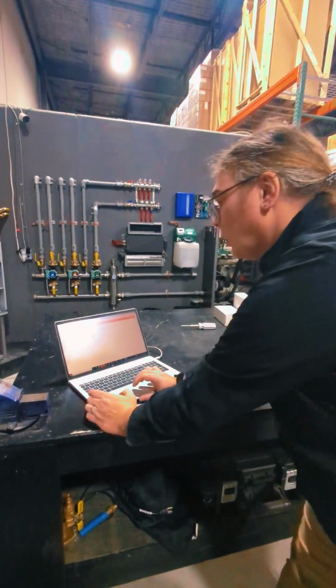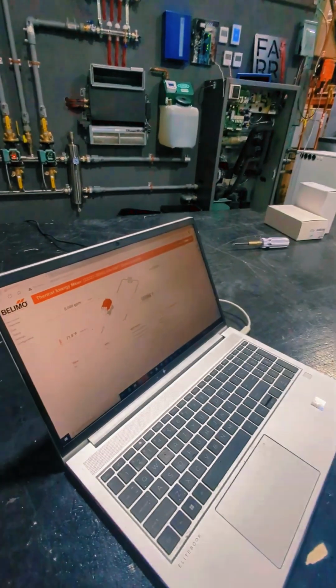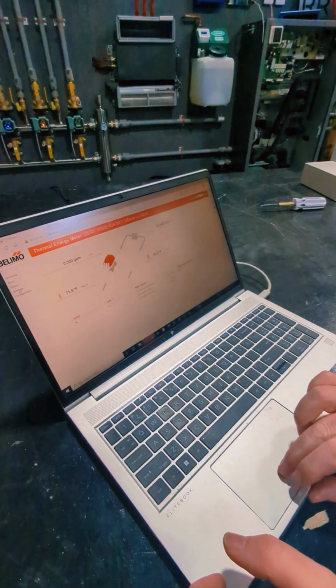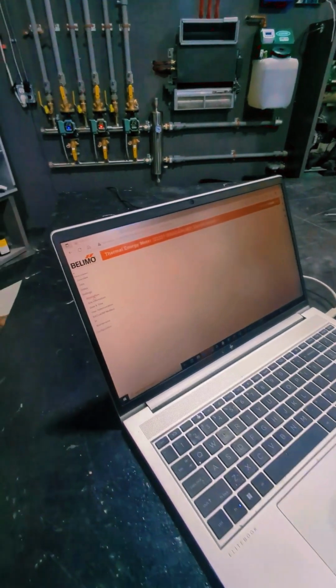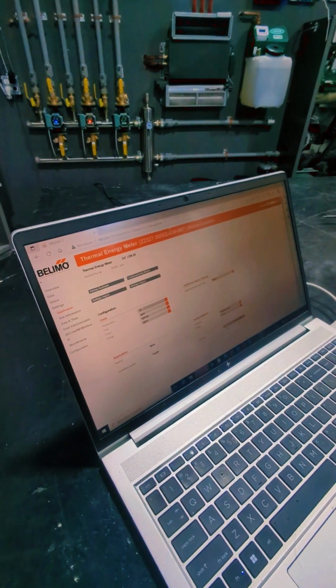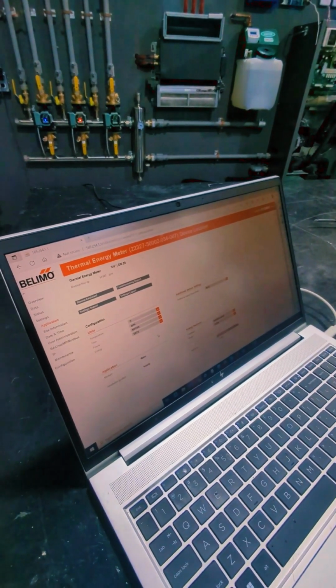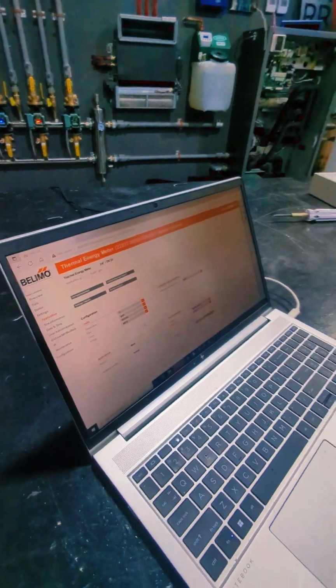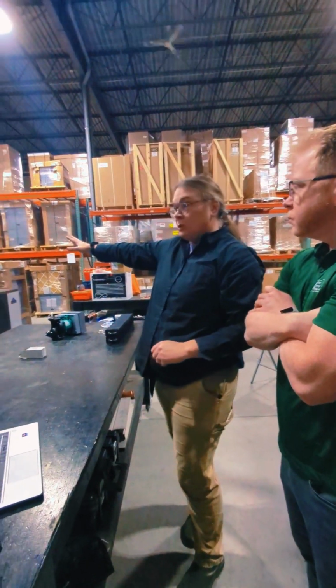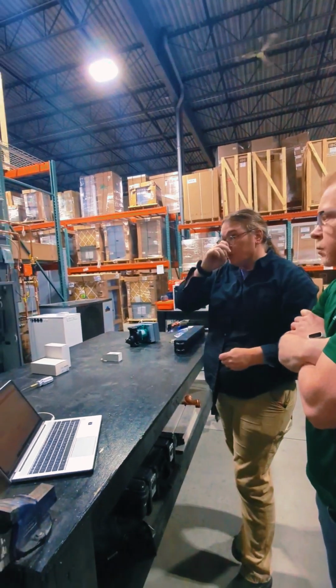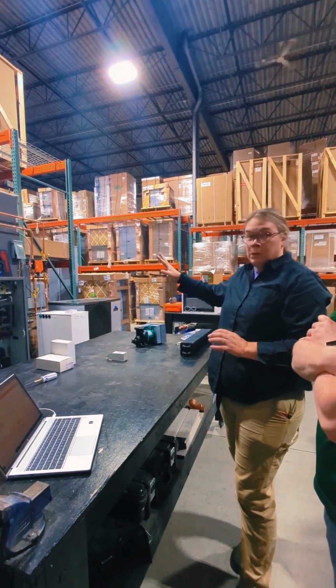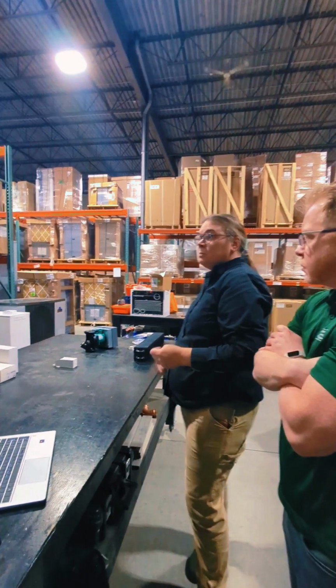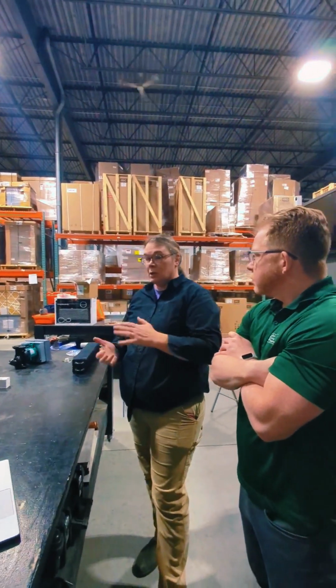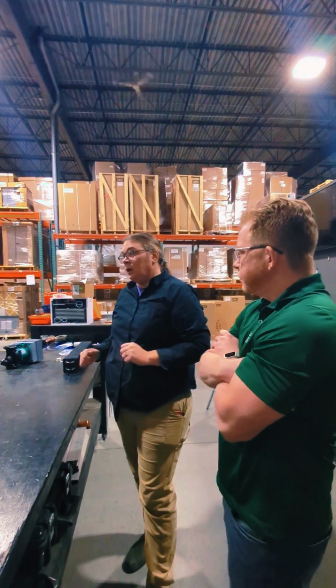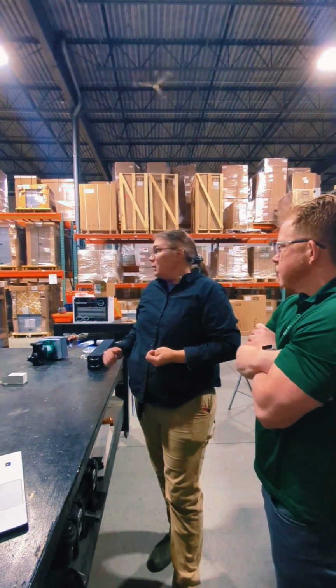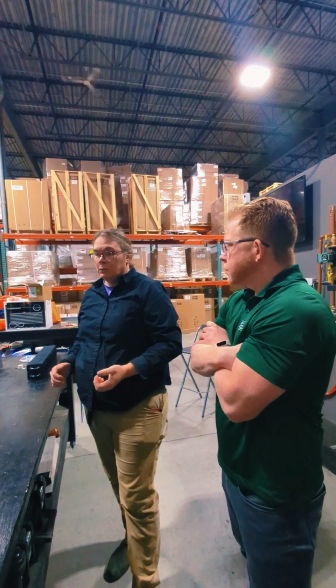All right. Exactly. So I've already logged into the thermal energy meter. I'm going to go into the settings menu and go to application. Now the application comes up and I'm able to set some other stuff up. So this setting here will change how that temperature sensor operates, but it won't affect the existing commissioning on the meter itself. Right. Because it's Measurement Canada certified, that meter commissioning is done once and never done again, because any changes after the fact would affect the certification of it.